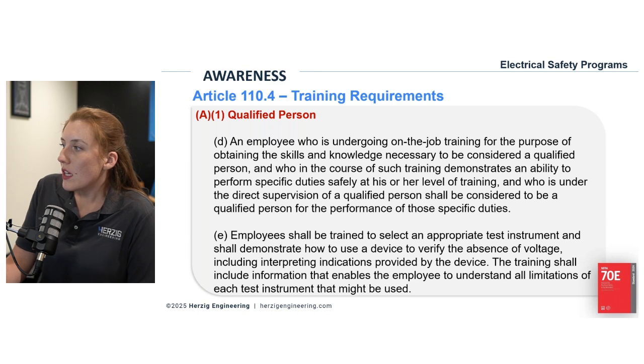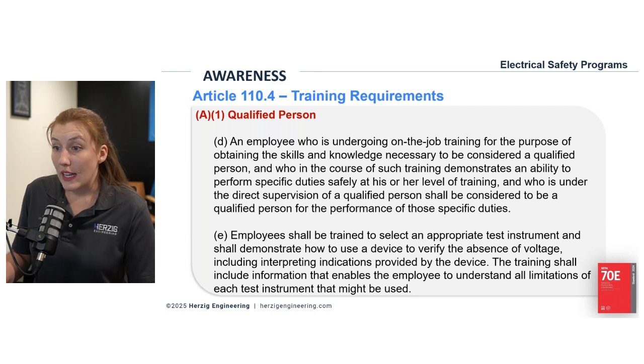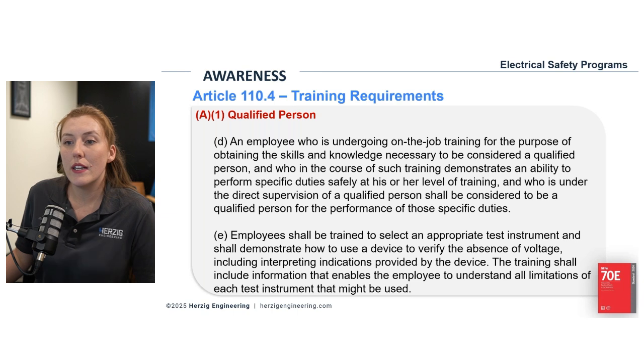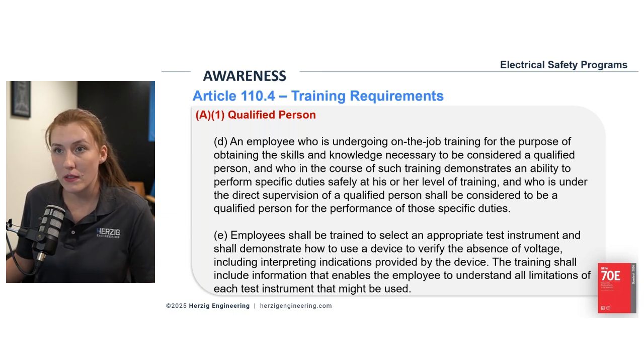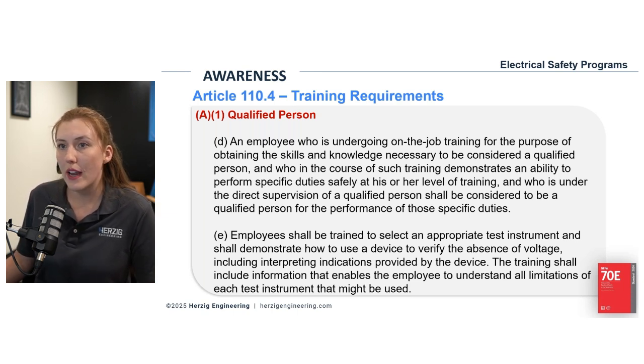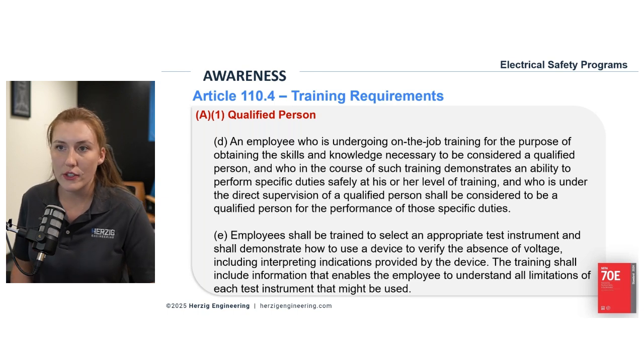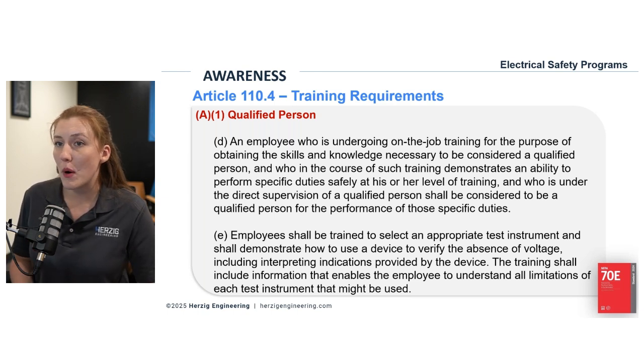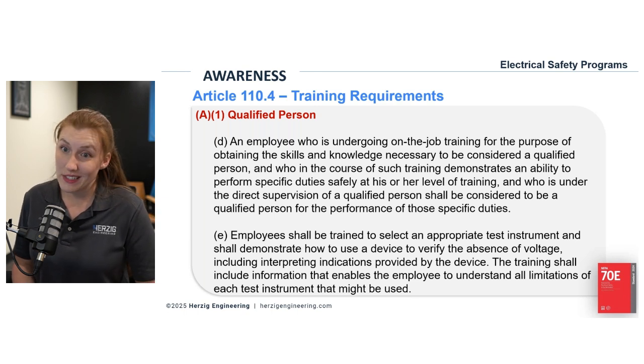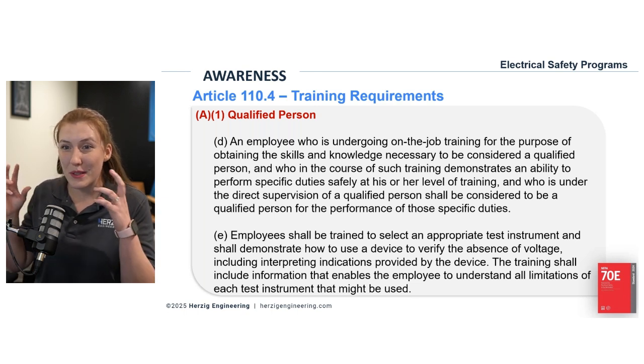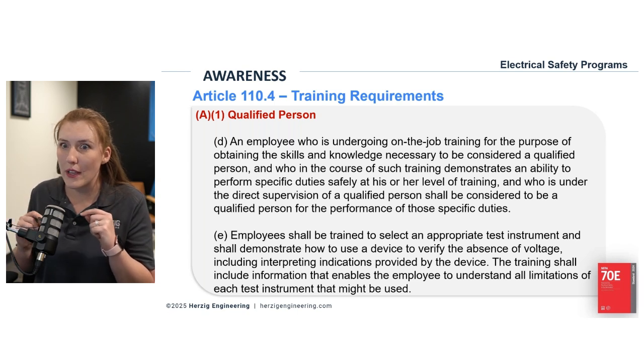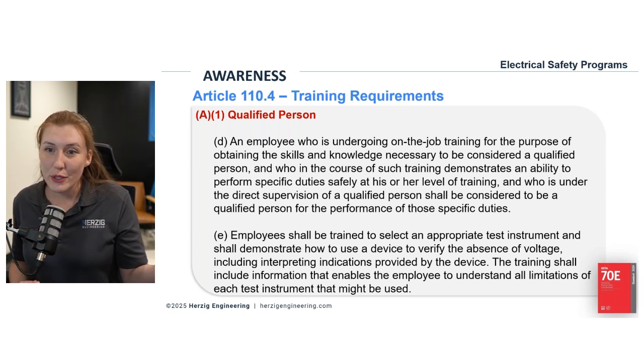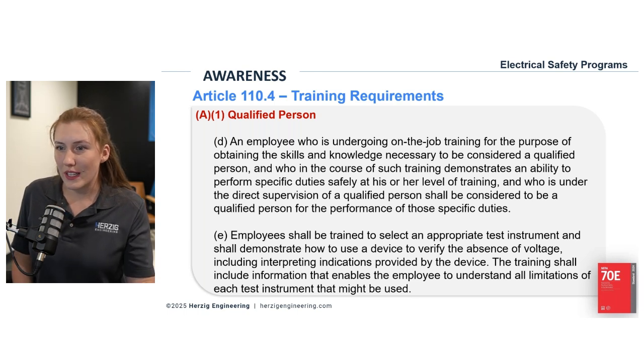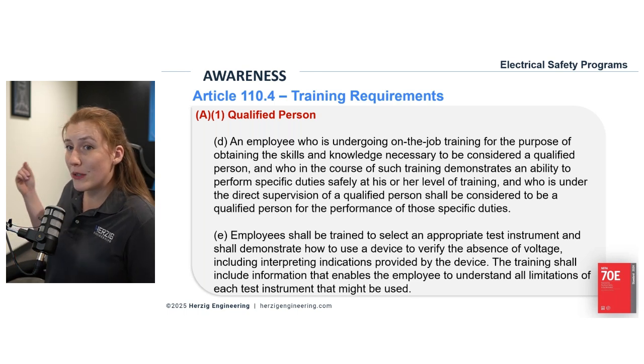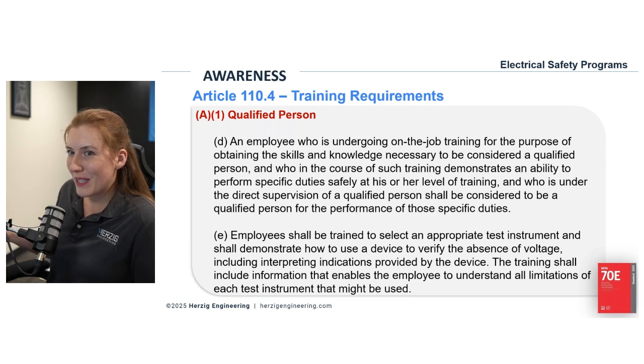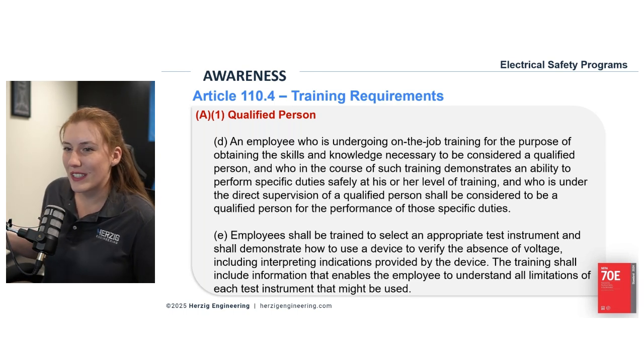A big part of training, and that's why it's got its own bullet point here, is verification of absence of voltage. They have to be trained on the steps to actually establish an electrically safe work condition. It is an 8-step process - I would argue more like 10 steps. If you went through my training, you'd know some of those steps have hidden steps within them, because you have to stop and put on your PPE before doing a step if there are exposed electrical conductors or circuit parts, and you also have to fill out a job safety plan because you're definitely going to be exposed to electrical conductors or circuit parts.